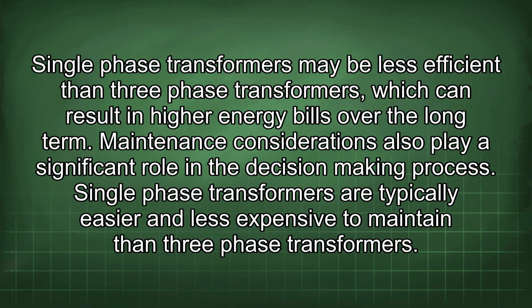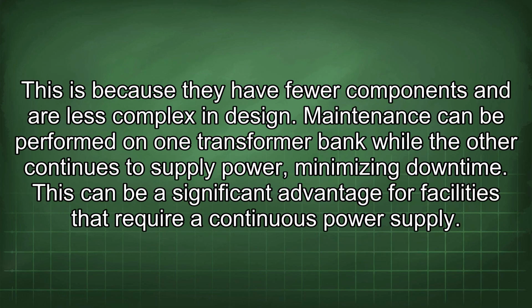Maintenance considerations also play a significant role in the decision-making process. Single-phase transformers are typically easier and less expensive to maintain than three-phase transformers. This is because they have fewer components and are less complex in design. Maintenance can be performed on one transformer bank while the other continues to supply power, minimizing downtime. This can be a significant advantage for facilities that require a continuous power supply.